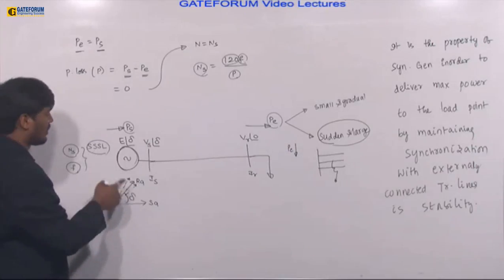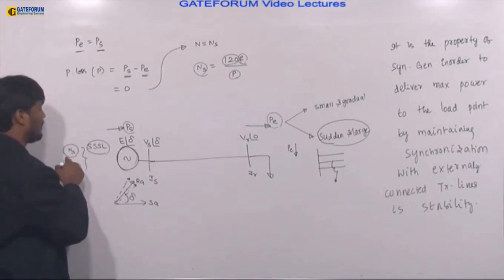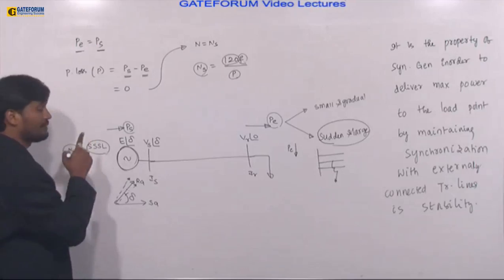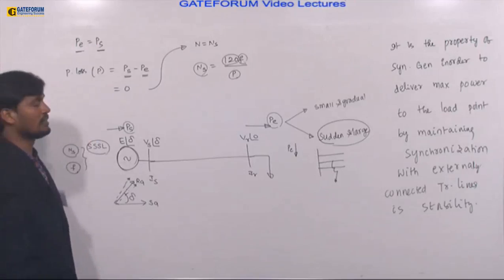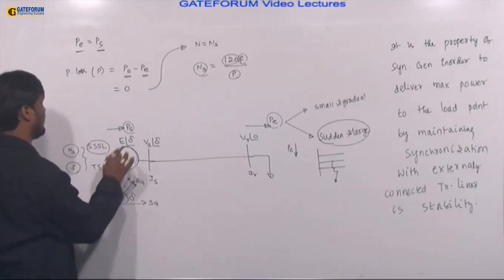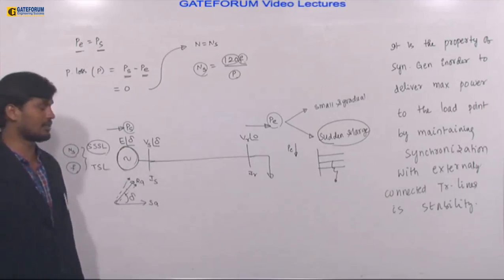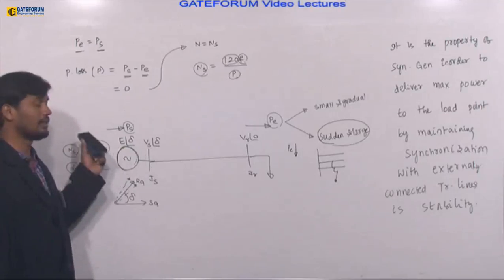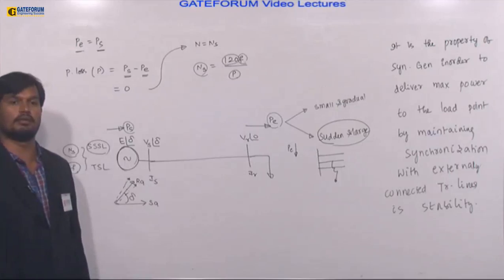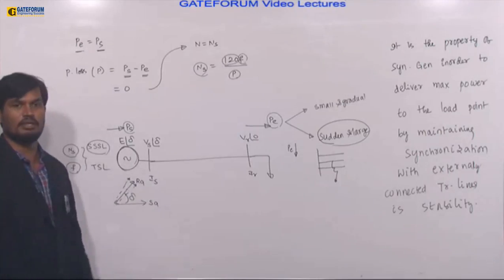The variation in load angle delta is also large, variation in speed is large, and variation in frequency is large. Therefore, this is dealing with transient stability, and it can be analyzed by a dynamic model, also called the swinging model, which we will discuss in depth.